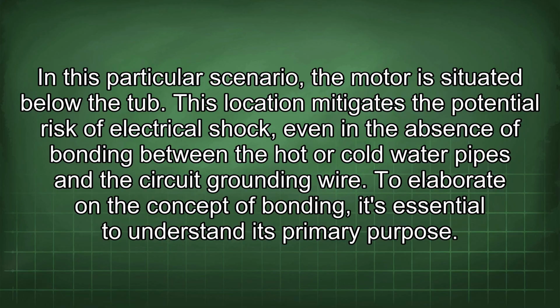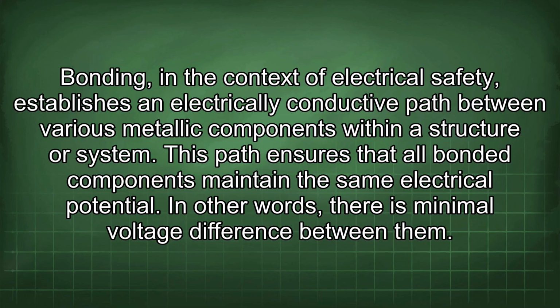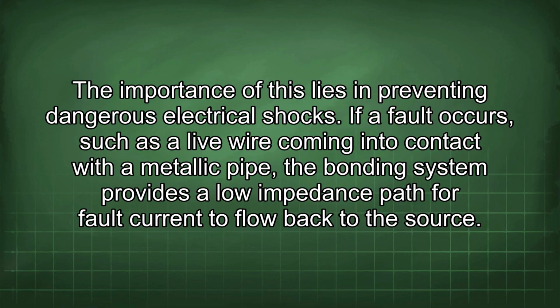To elaborate on the concept of bonding, it's essential to understand its primary purpose. Bonding, in the context of electrical safety, establishes an electrically conductive path between various metallic components within a structure or system. This path ensures that all bonded components maintain the same electrical potential. In other words, there is minimal voltage difference between them. The importance of this lies in preventing dangerous electrical shocks.